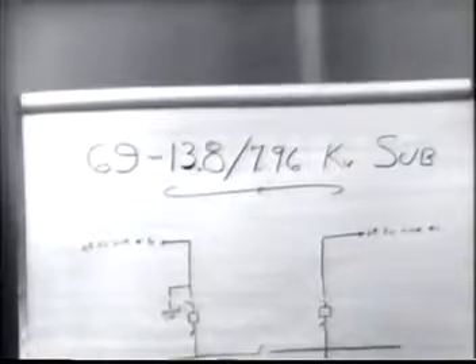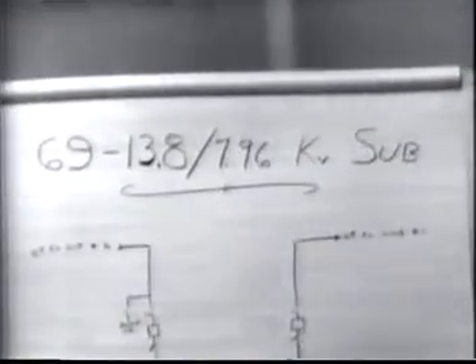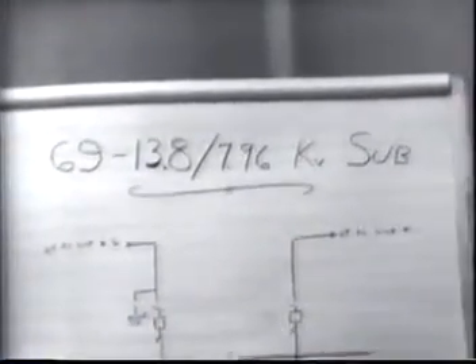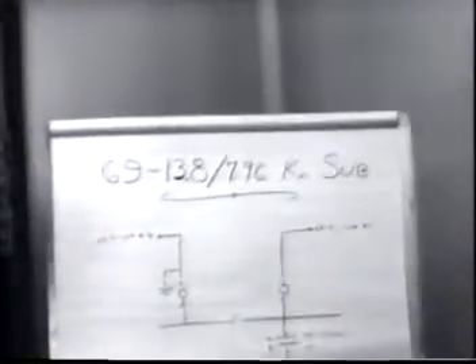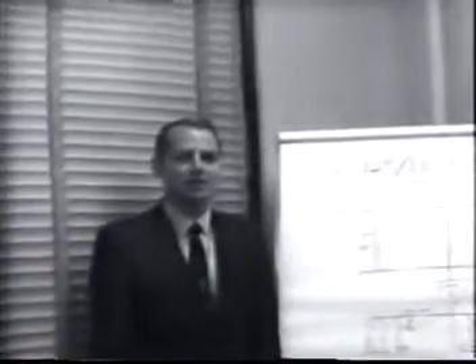This was the establishment of a 13-8, 7960 grounded Y type of distribution system. The distribution transformers and circuits are sometimes called 13-2/7620 system, but basically what they mean is you have a distribution line, 3 phase wires and 1 neutral.